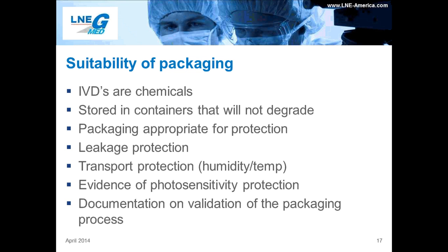So, for example, in the case of lateral flow assays, humidity changes have a major impact on your device. Any evidence of photosensitivity protection, obviously light-sensitive devices are not going to be packaged in clear bottles, and any documentation on the validation of the packaging process should also be included.